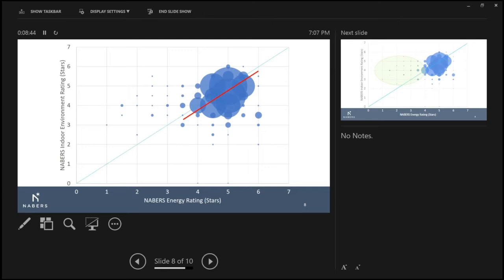Similarly with fan energy — fans in the initial fit-out of a building are air balanced nicely, but as tenants move in and out, walls move, meeting rooms get added, office layouts change. Air balancing isn't always addressed in the tenant fit-out, since it's often treated as a base building responsibility, base building loading. So we see that imbalance grow over time.